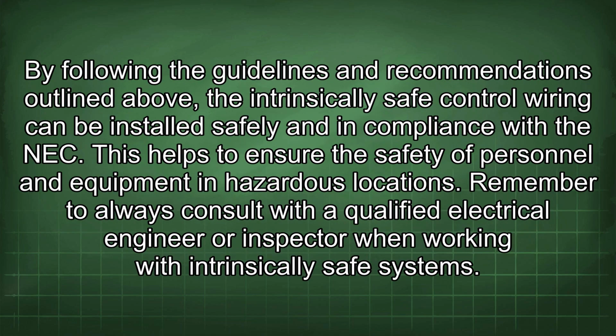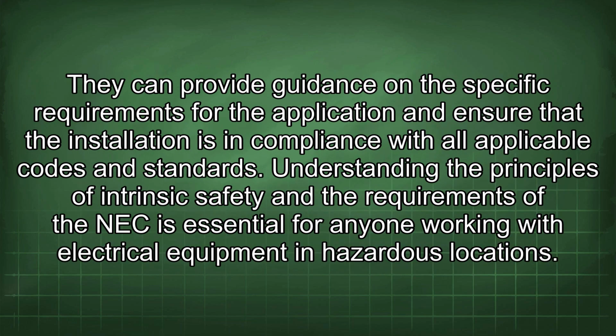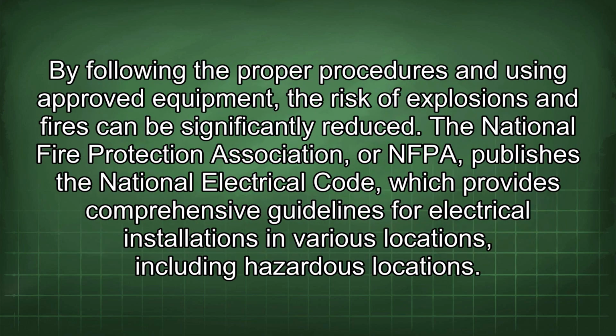By following the guidelines and recommendations outlined above, the intrinsically safe control wiring can be installed safely and in compliance with the NEC. This helps to ensure the safety of personnel and equipment in hazardous locations. Remember to always consult with a qualified electrical engineer or inspector when working with intrinsically safe systems. They can provide guidance on the specific requirements for the application and ensure that the installation is in compliance with all applicable codes and standards. Understanding the principles of intrinsic safety and the requirements of the NEC is essential for anyone working with electrical equipment in hazardous locations. By following the proper procedures and using approved equipment, the risk of explosions and fires can be significantly reduced.